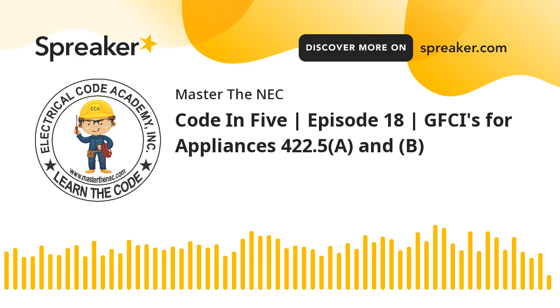All right, so what are the appliances that require GFCI protection? 422.5(A) says appliances identified in 422.5(A)(1) through (A)(7) rated 150 volts or less to ground and 60 amperes or less, single or three-phase, shall be provided with Class A GFCI protection. It does tell us that we can have multiple GFCIs in series, and it's not going to change their function. It's unnecessary, but it says that it's okay if you do that. They're going to work fine, not a problem.